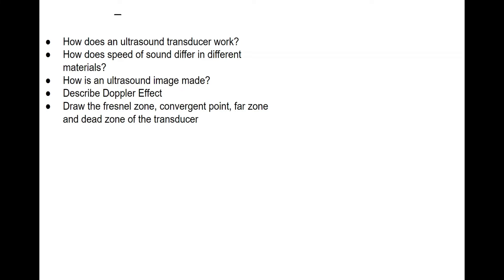At a high level, the transducer takes electric signals and converts them to mechanical signals. It relies on piezoelectric crystals to make sound pressure waves at different frequencies, typically 3-7 megahertz. The crystal is normally lead zirconate titanate. When it feels pressure, it converts that to an electric signal. That's how the transducer works and how you get your electrical signal.